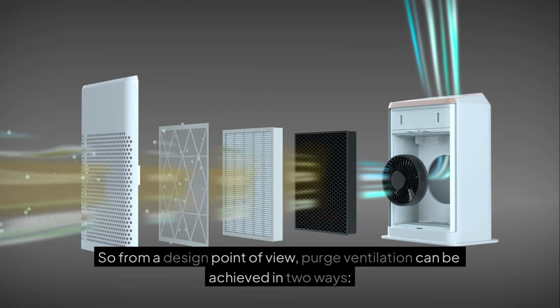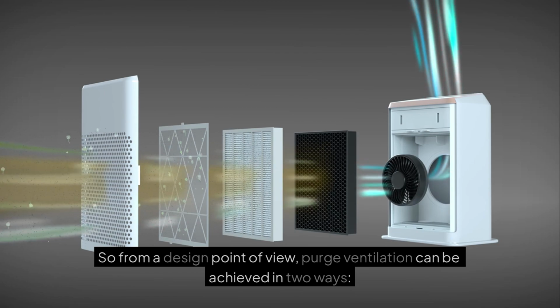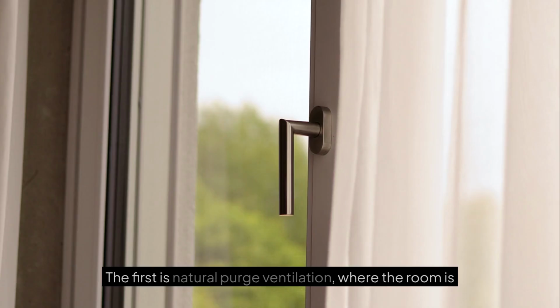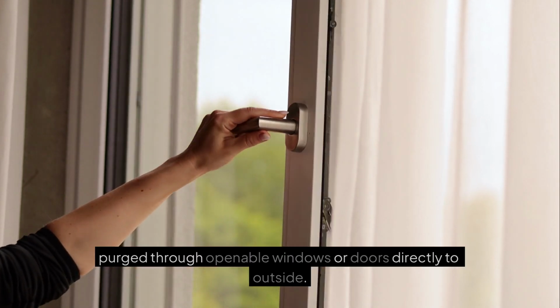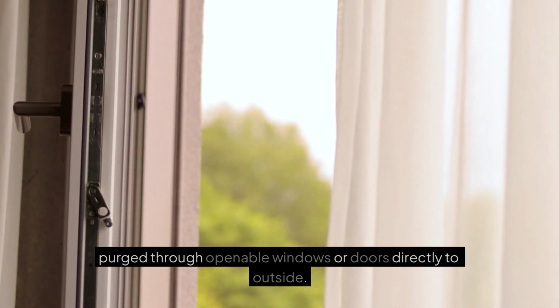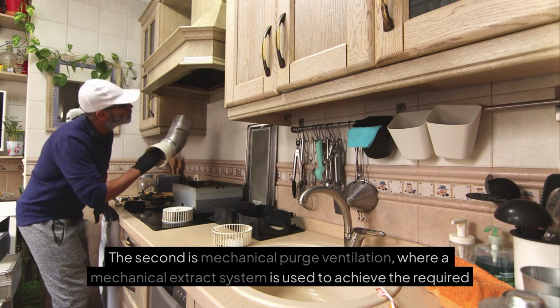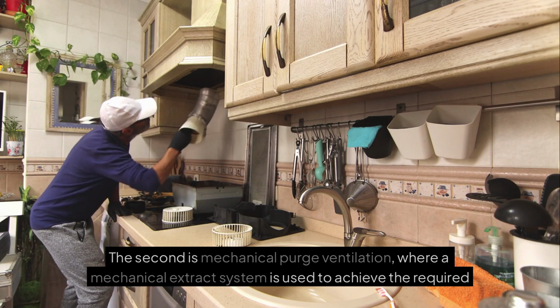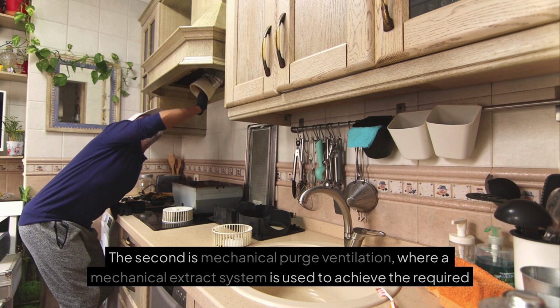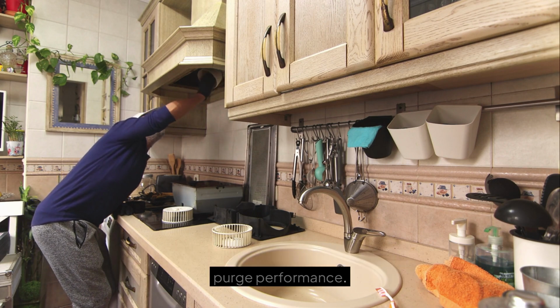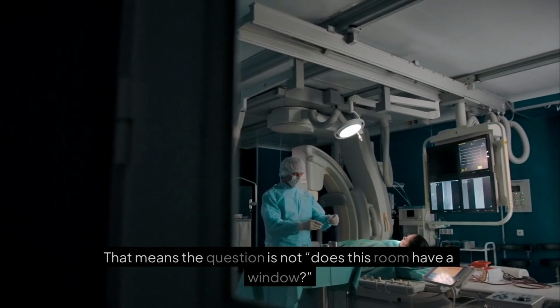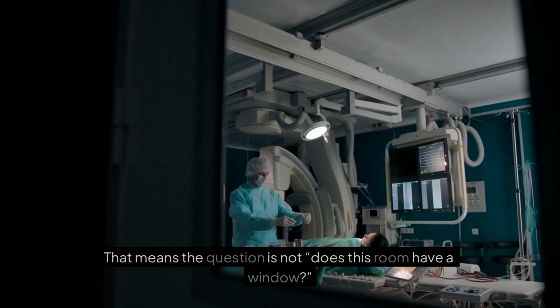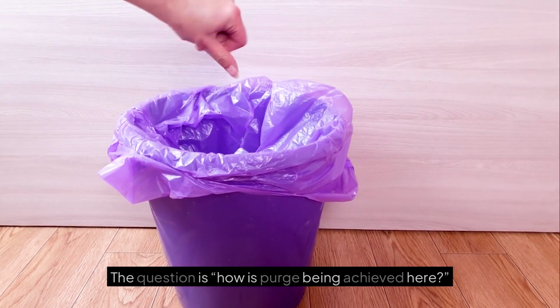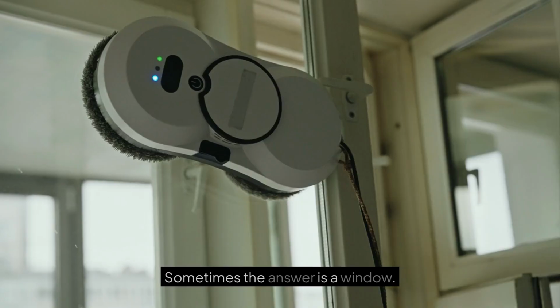So from a design point of view, purge ventilation can be achieved in 2 ways. The first is natural purge ventilation, where the room is purged through openable windows or doors directly to outside. The second is mechanical purge ventilation, where a mechanical extract system is used to achieve the required purge performance. That means the question is not, does this room have a window? The question is, how is purge being achieved here?